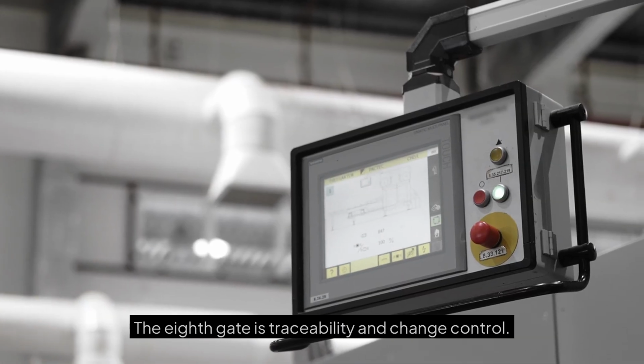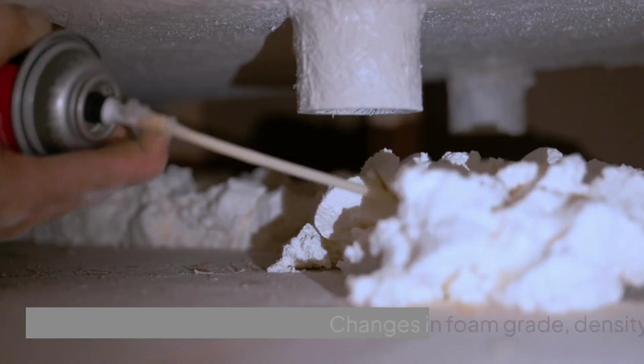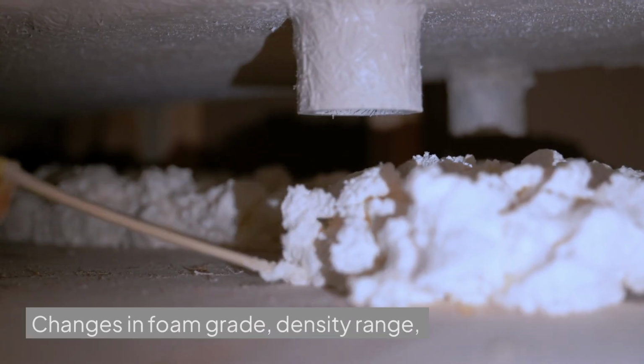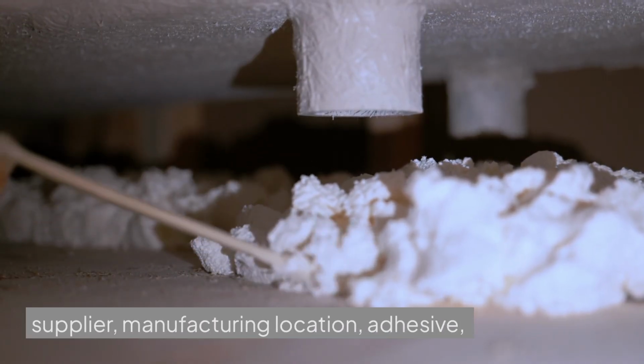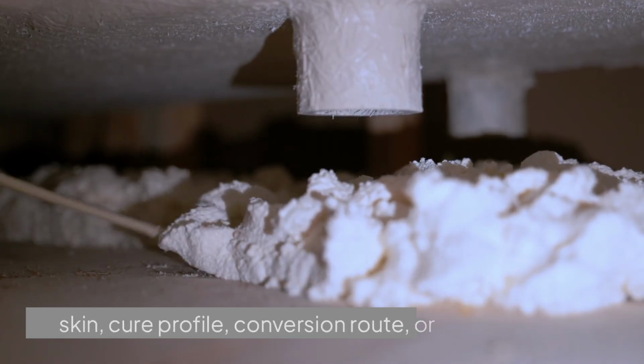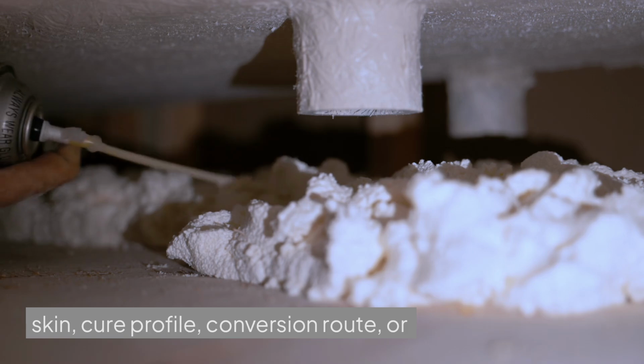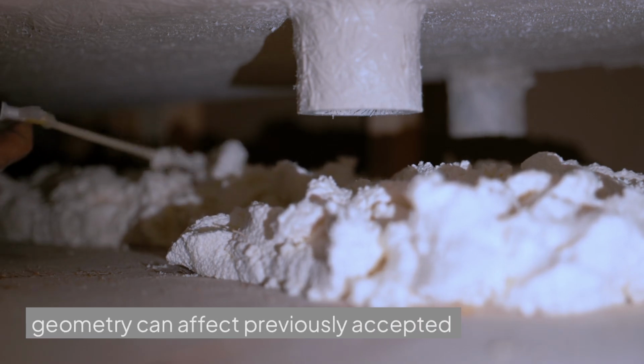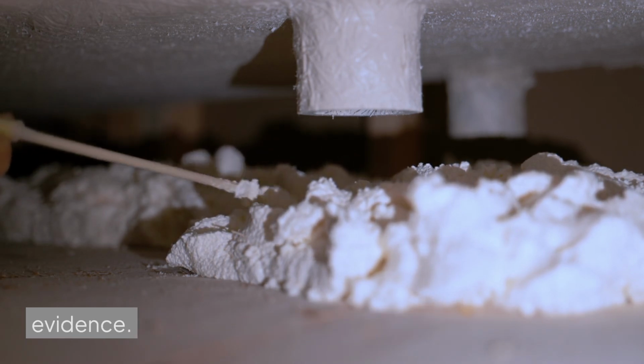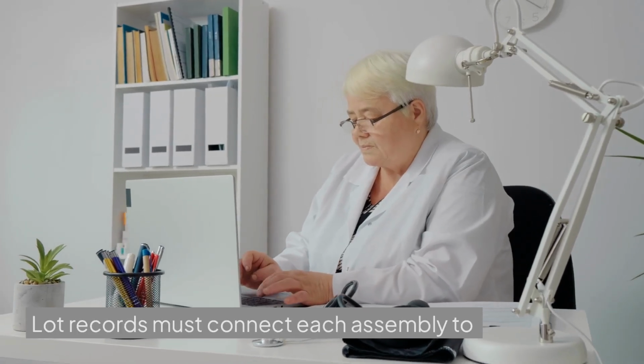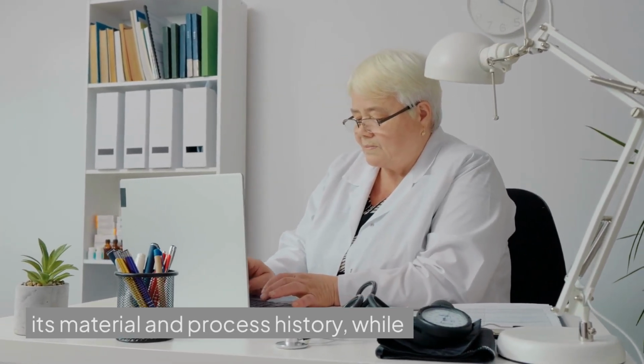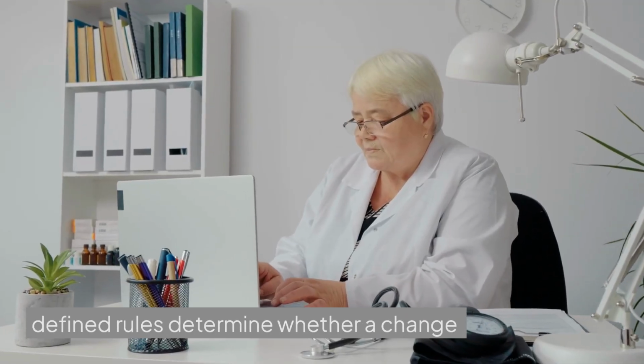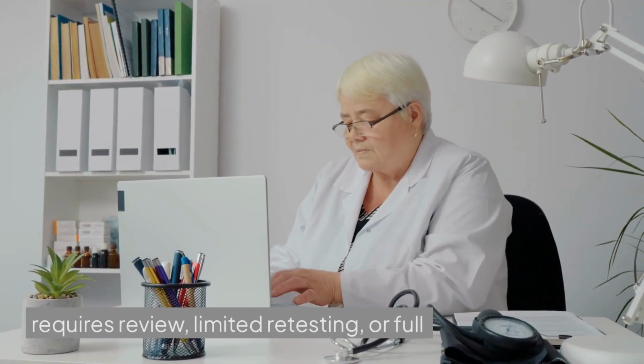The eighth gate is traceability and change control. Changes in foam grade, density range, supplier, manufacturing location, adhesive, skin, cure profile, conversion route, or geometry can affect previously accepted evidence. Lot records must connect each assembly to its material and process history, while defined rules determine whether a change requires review, limited retesting, or full requalification.